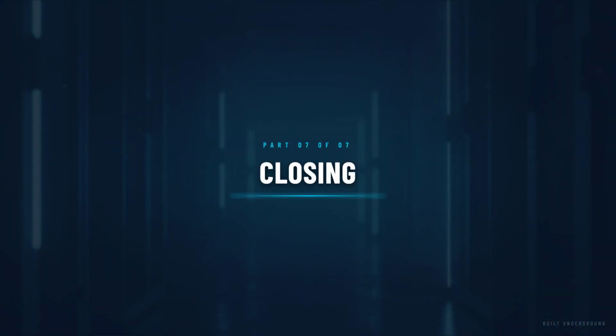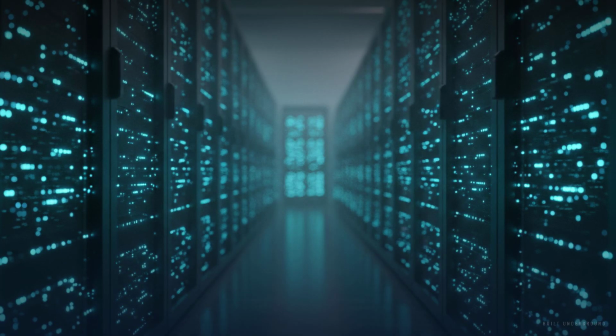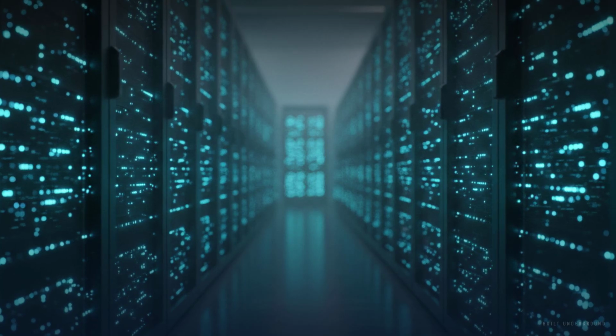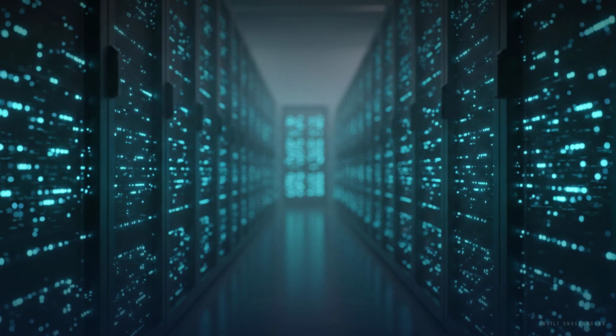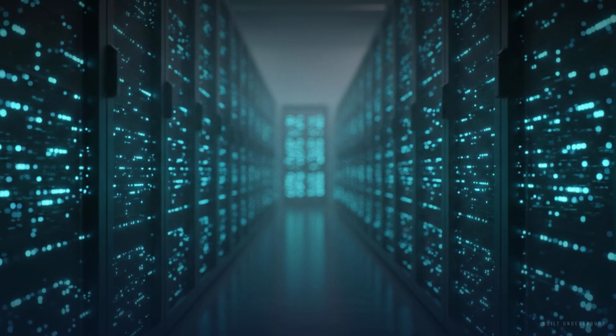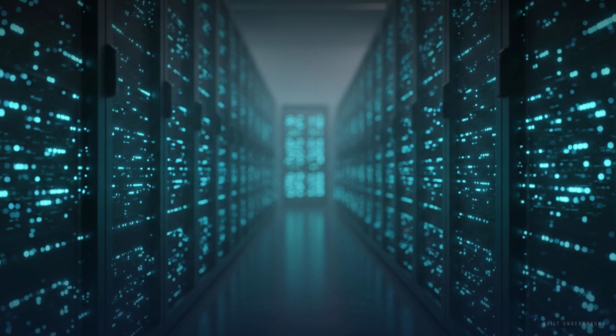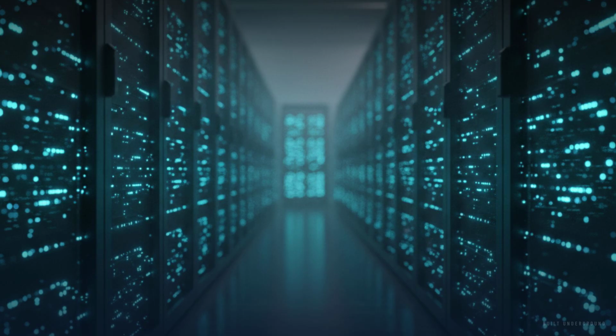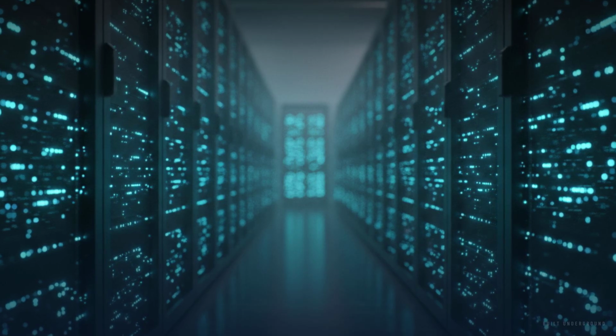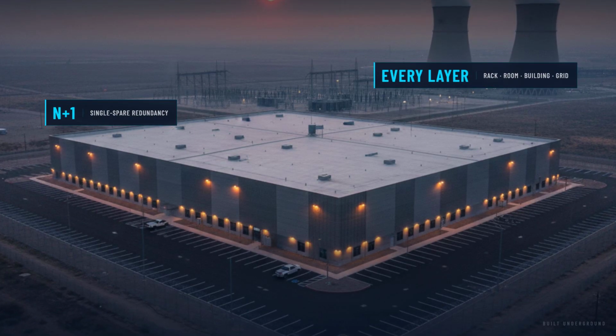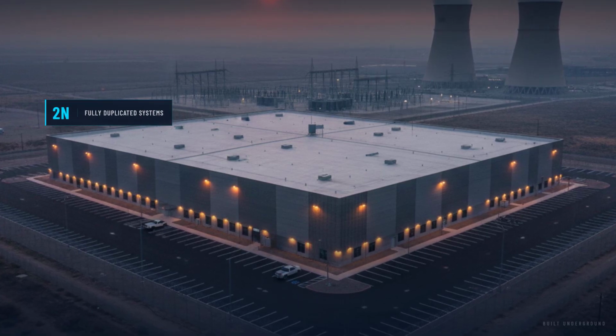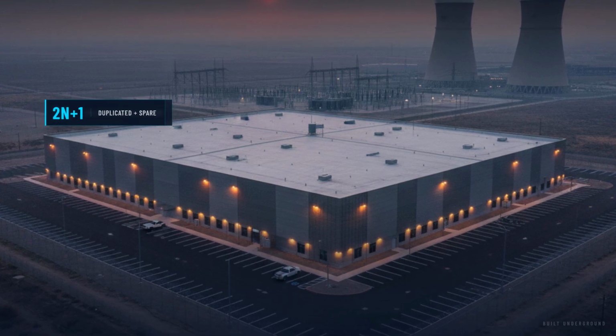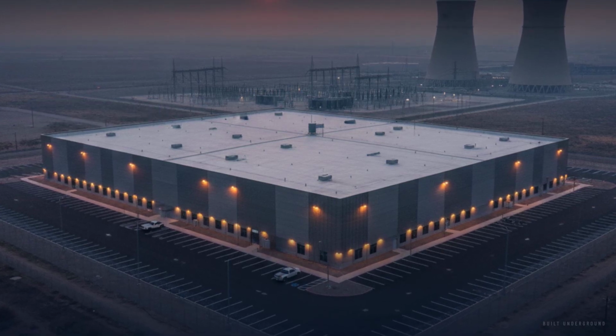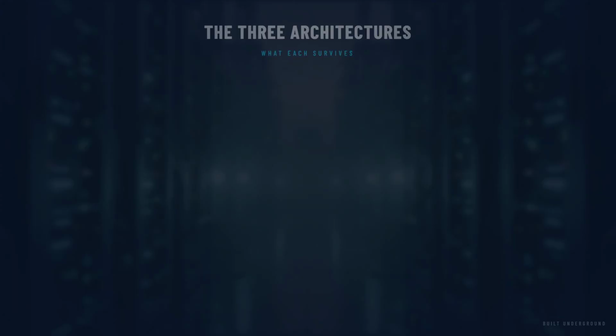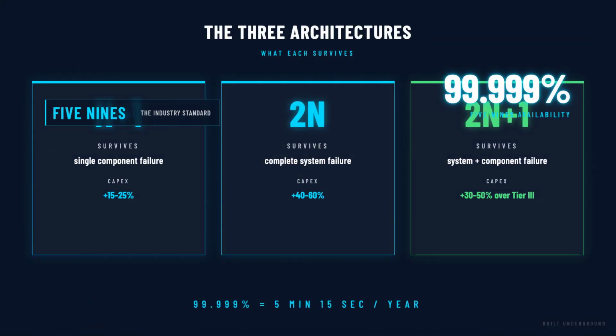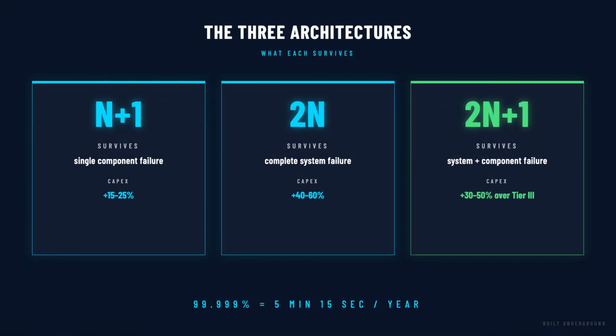The next time you stream a video, make a bank transfer, or ask an AI a question, the response arrives in milliseconds. Behind that speed is an engineering philosophy that assumes failure is inevitable and designs around it. N+1 survives a component failure. 2N survives a system failure. 2N+1 survives a system failure plus a component failure on the surviving system, and 5 nines, 99.999%, 5 minutes of downtime per year, is the result.